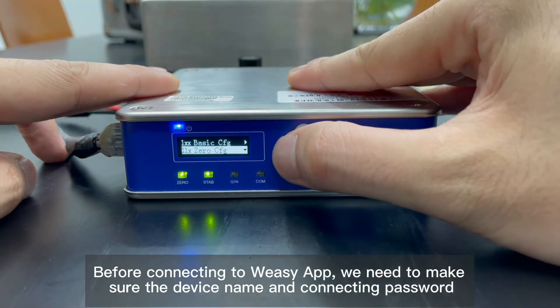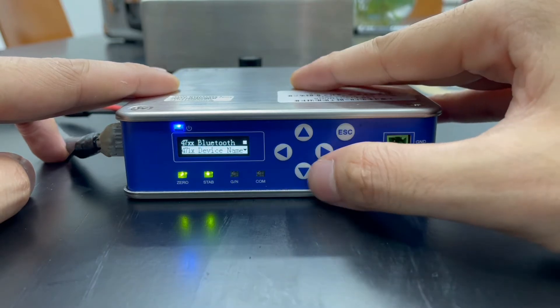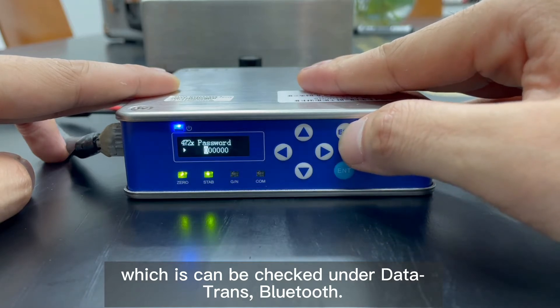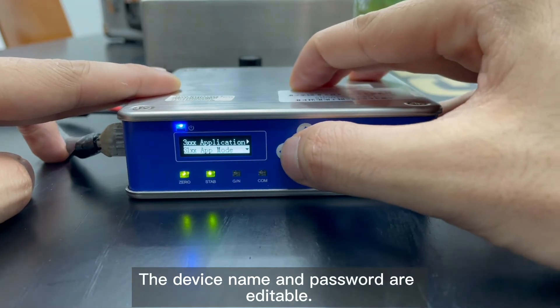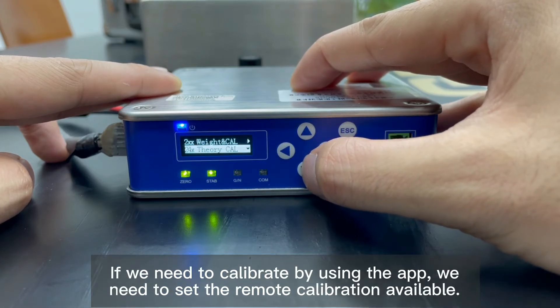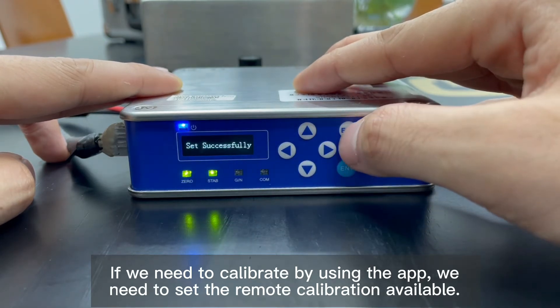Before connecting to Weasy App, we need to make sure of the device name and connecting password, which can be checked under Datatrans Bluetooth. The device name and password are editable. If we need to calibrate using the app, we need to set remote calibration as available.